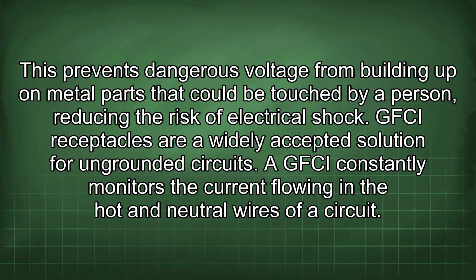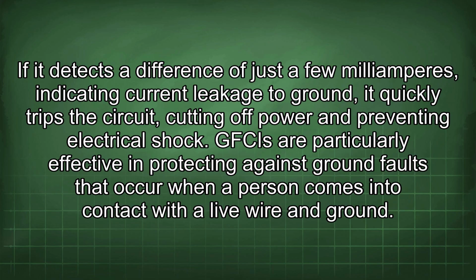A GFCI constantly monitors the current flowing in the hot and neutral wires of a circuit. If it detects a difference of just a few milliamperes, indicating current leakage to ground, it quickly trips the circuit, cutting off power and preventing electrical shock. GFCIs are particularly effective in protecting against ground faults that occur when a person comes into contact with a live wire and ground.